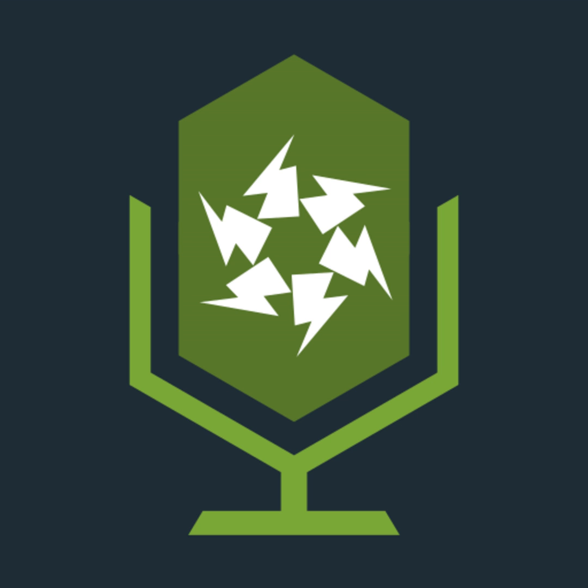With colour, neutral or midpoint. If a circuit includes a neutral or midpoint conductor identified by colour, the colour will be blue. The protective conductor. The bicolour combination of green and yellow will be used exclusively for the identification of a protective conductor. This combination shall not be used for any other purpose, and with this combination, one of the colours will cover at least 30% and at most 70% of the surface to be coloured. So when you come to the yellow and green, you need to have no more than 70% of that being one colour and no less than 30% being the other.